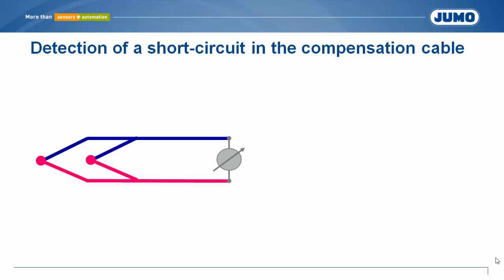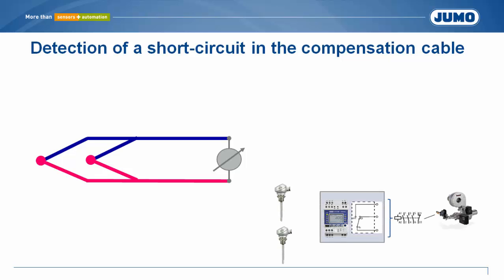Two thermocouples are used for safety-relevant applications, such as the use of safety temperature limiters. The temperature of the thermocouples is measured by two separate inputs, and the temperature deviation is determined. If a temperature deviation defined in the field device is exceeded, an error message is indicated on the field device. Respectively, the process is switched off. A short circuit in a compensation cable is detected in this way.